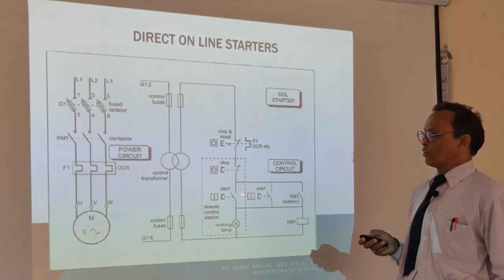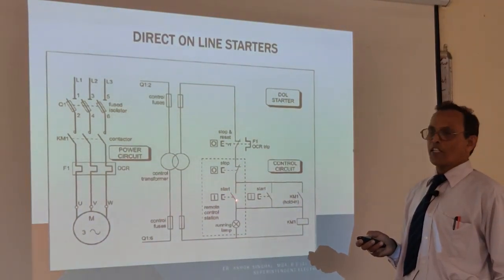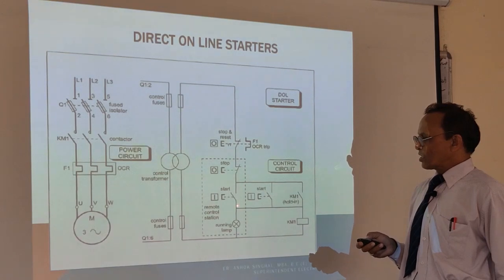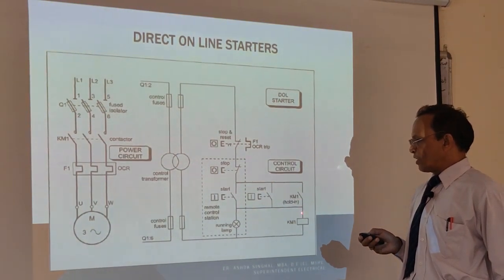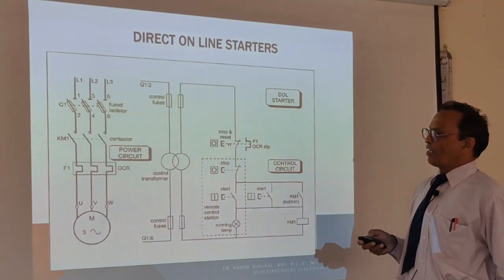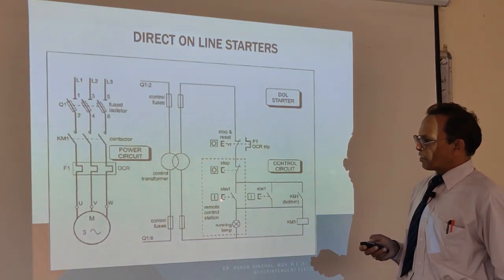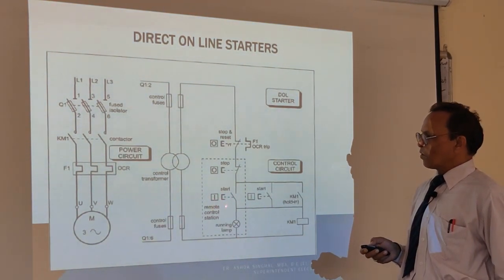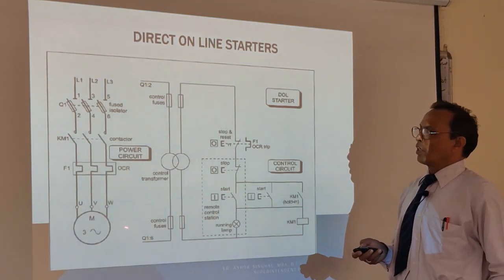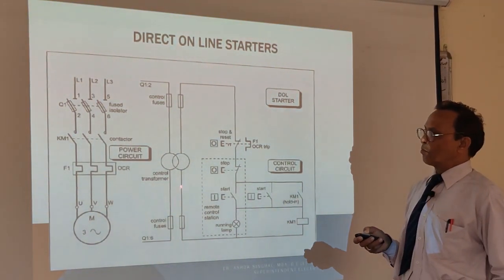At the same time, the holding-on contact is made. The holding contact is a retaining contact. So the moment you release the start push button, power will flow through the holding contact instead — the circuit remains complete and your motor keeps running. So this is the remote start. You can press either one of the remote start buttons and your motor will start running and keep on working.